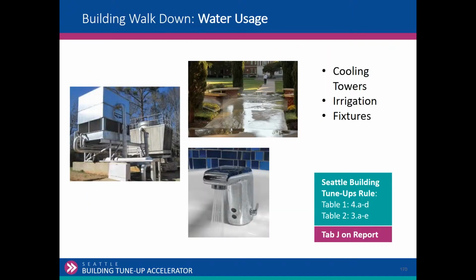If you notice missing pipe insulation or whatever, you can note in your report that there's a bunch of missing pipe. It should be insulated. You can use a thermal imaging camera and pretty easily determine whether that's hot water piping, cold water piping, or recirculated water piping. You'd want to note that. That's a relatively low cost thing. It's not required, but insulating the piping does reduce energy use. So that's on the hot water side.